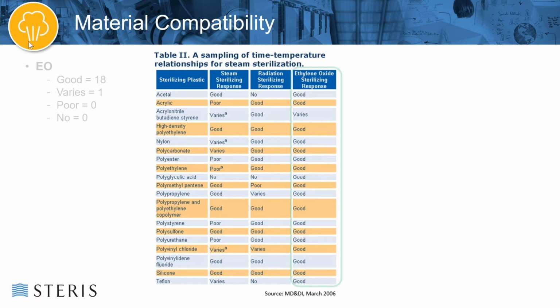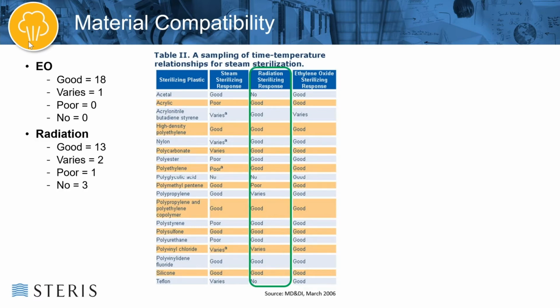So for those of you who are numbers people, what this essentially boils down to is that on this table there's 18 materials that are good for EO and only one that varies, and there are no poor and no that cannot be sterilized with EO. For radiation, we have 13 of these materials that are good, 2 of them vary. There's 1 poor and there's 3 of them that you cannot process with radiation.